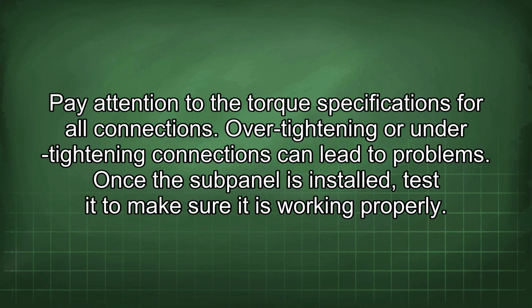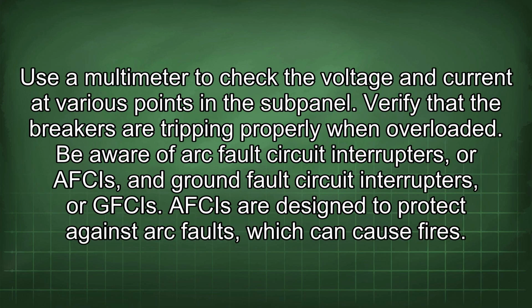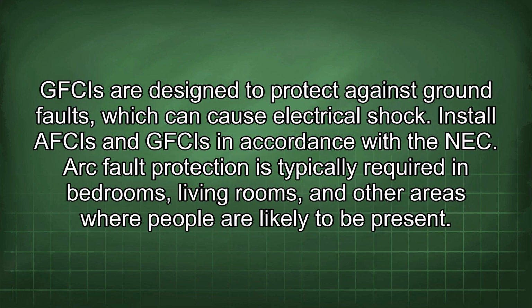Once the subpanel is installed, test it to make sure it is working properly. Use a multimeter to check the voltage and current at various points in the subpanel. Verify that the breakers are tripping properly when overloaded. Be aware of arc fault circuit interrupters, or AFCIs, and ground fault circuit interrupters, or GFCIs. AFCIs are designed to protect against arc faults, which can cause fires. GFCIs are designed to protect against ground faults, which can cause electrical shock.